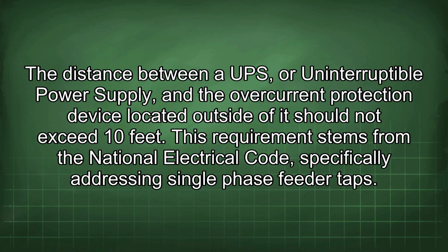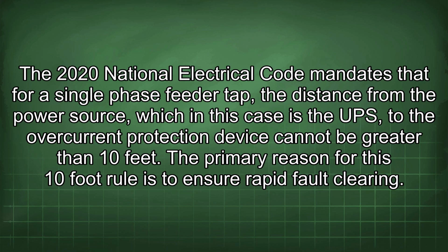The distance between a UPS, or uninterruptible power supply, and the overcurrent protection device located outside of it should not exceed 10 feet. This requirement stems from the National Electrical Code, specifically addressing single-phase feeder taps. The 2020 National Electrical Code mandates that for a single-phase feeder tap, the distance from the power source, which in this case is the UPS, to the overcurrent protection device cannot be greater than 10 feet.